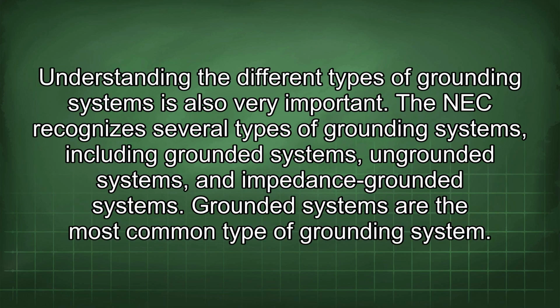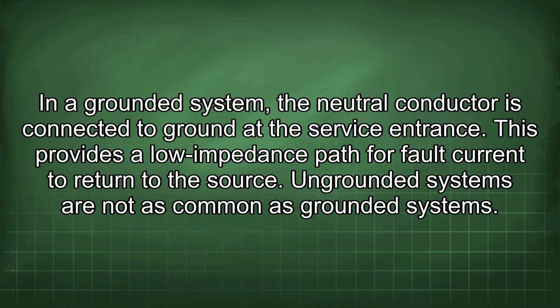Understanding the different types of grounding systems is also very important. The NEC recognizes several types of grounding systems, including grounded systems, ungrounded systems, and impedance-grounded systems. Grounded systems are the most common type of grounding system. In a grounded system, the neutral conductor is connected to ground at the service entrance. This provides a lower impedance path for fault current to return to the source.